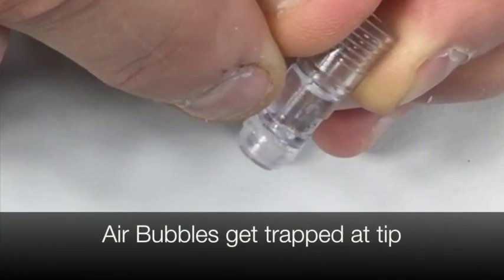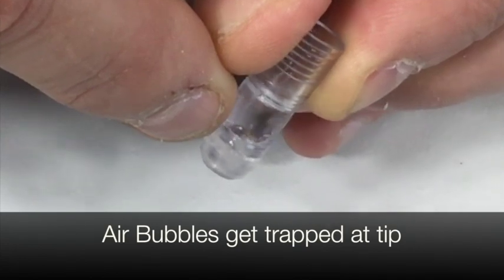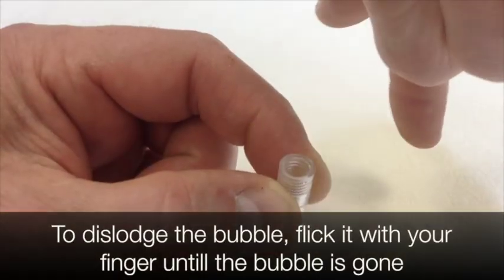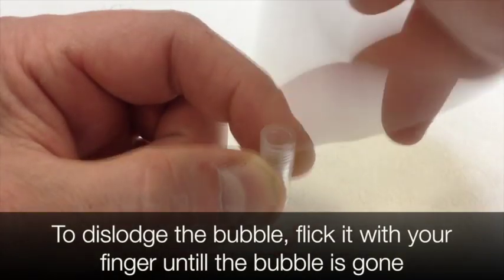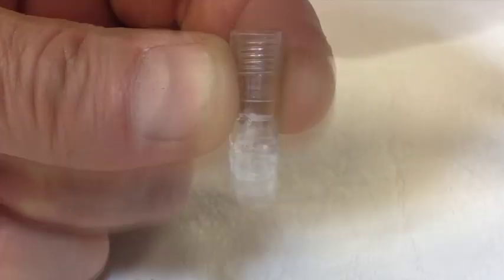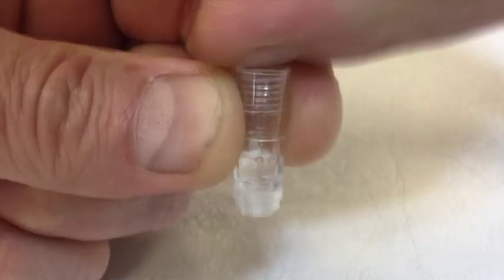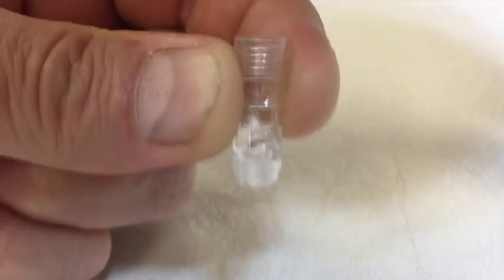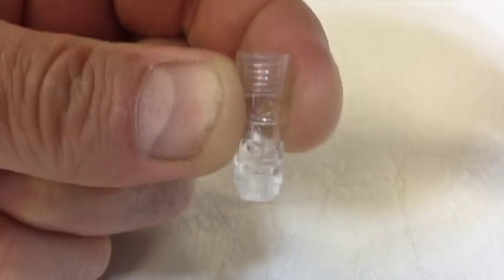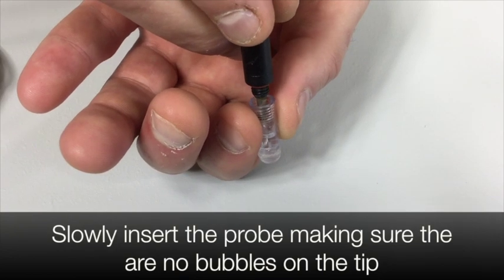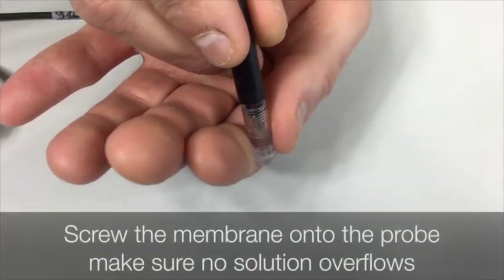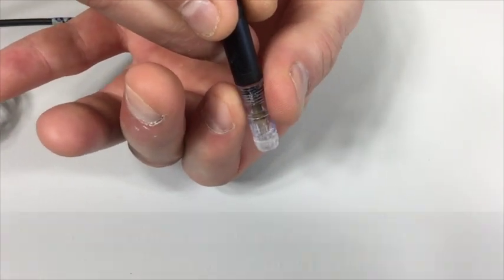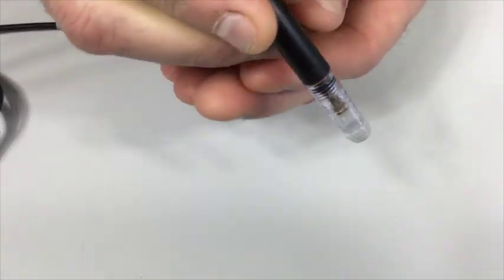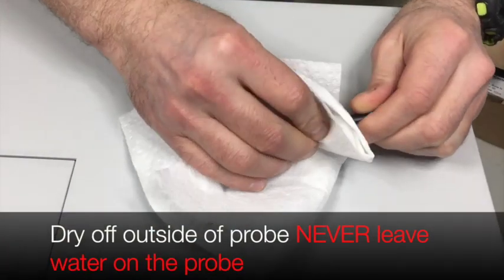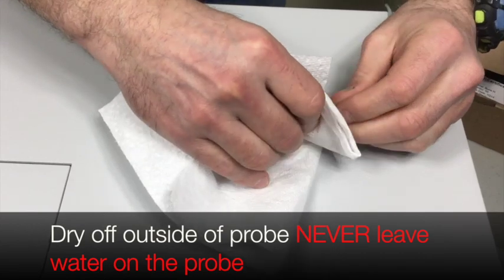You will always get an air bubble trapped at the tip of the membrane. Using your fingernail, tap the top of the membrane jacket until you dislodge all the bubbles as shown in the video. Slowly insert the probe, making sure that there are no air bubbles on the tip. Screw the membrane onto the probe and make sure the solution does not overflow. Dry off the probe. Never leave water on the probe.